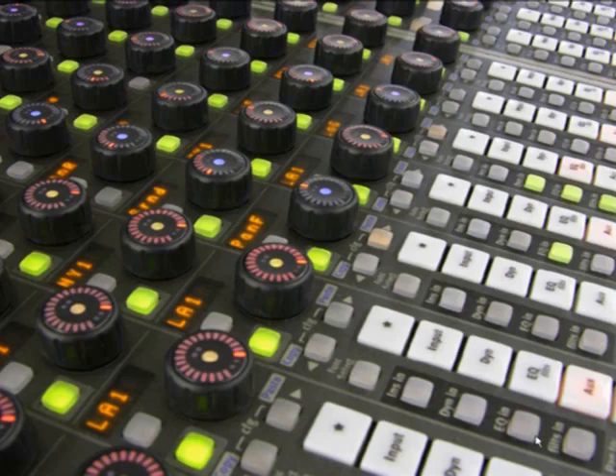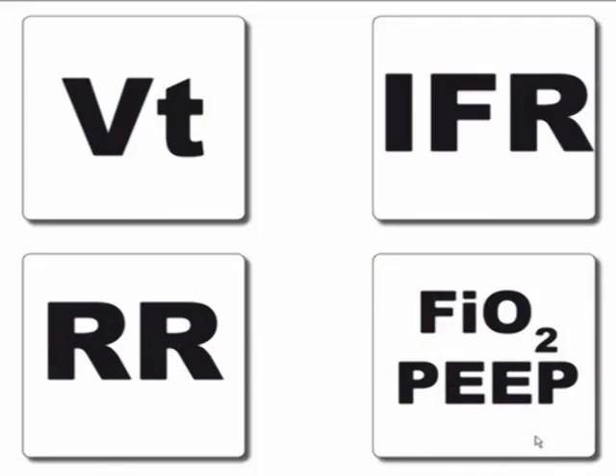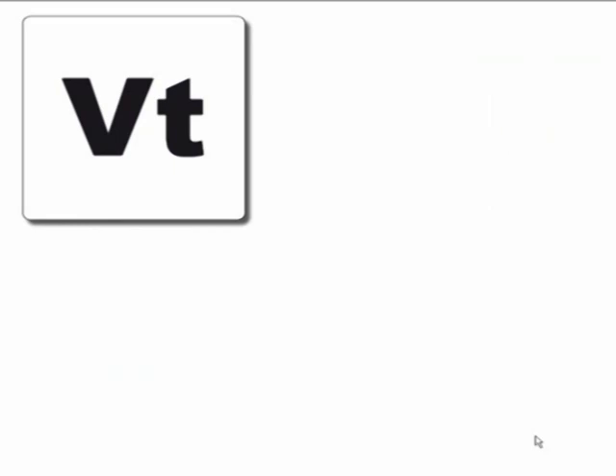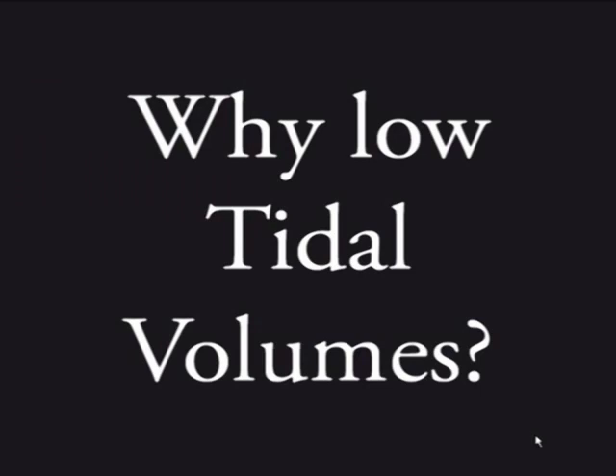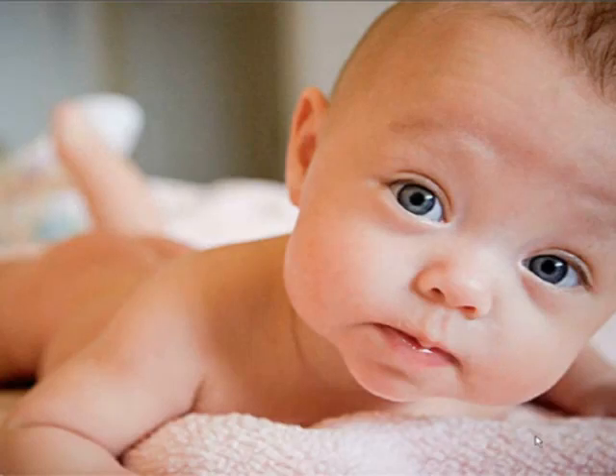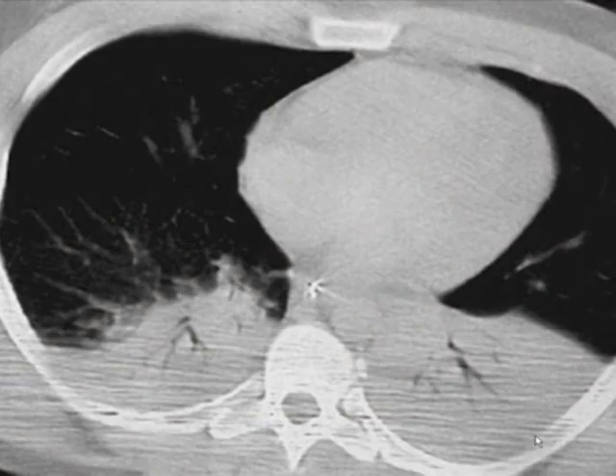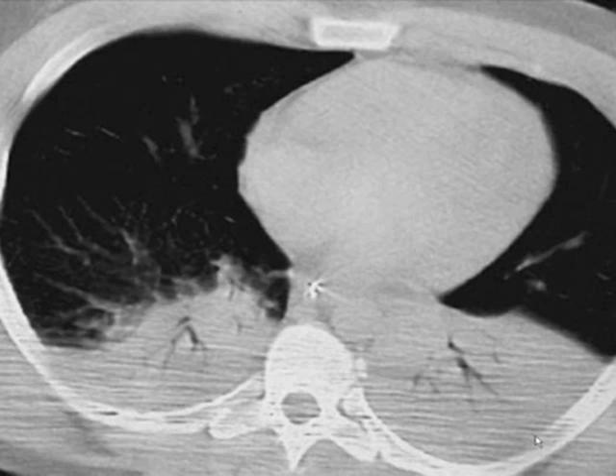You have a ton of other dials — what do they mean? We can split them into four and discuss each one. First is tidal volume — that's what 'VT' means. Years ago they used very high tidal volumes, and that was injurious; that's where all the lung injury came from. To understand why we use low tidal volumes: injured lungs are baby lungs — 'bambino lungs,' as first coined by an Italian. Look at those dependent lung portions — that's consolidation. Those lung areas are not getting any of the tidal volume you put in.